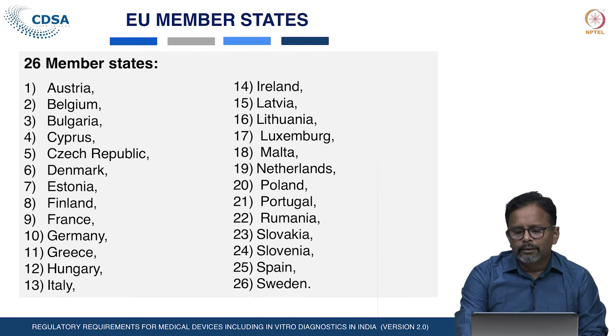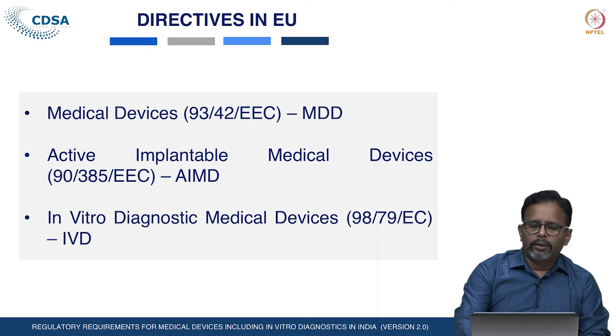the medical device directive, that is medical device directive 93/42/EEC, is for medical devices. Another directive, 90/385/EEC, is for active implantable medical devices, and directive 98/79/EC is applicable for in vitro diagnostic medical devices. These 3 directives cover the regulation of medical devices in Europe.